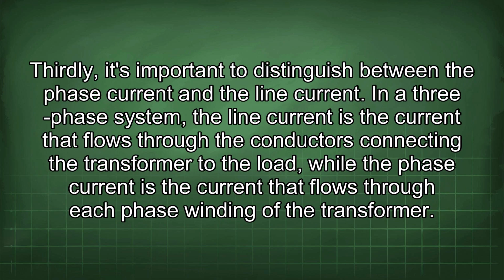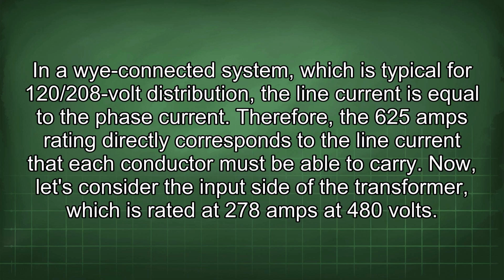Thirdly, it's important to distinguish between the phase current and the line current. In a three-phase system, the line current is the current that flows through the conductors connecting the transformer to the load, while the phase current is the current that flows through each phase winding of the transformer. In a Y-connected system, which is typical for 120/208 volt distribution, the line current is equal to the phase current. Therefore, the 625 amps rating directly corresponds to the line current that each conductor must be able to carry.